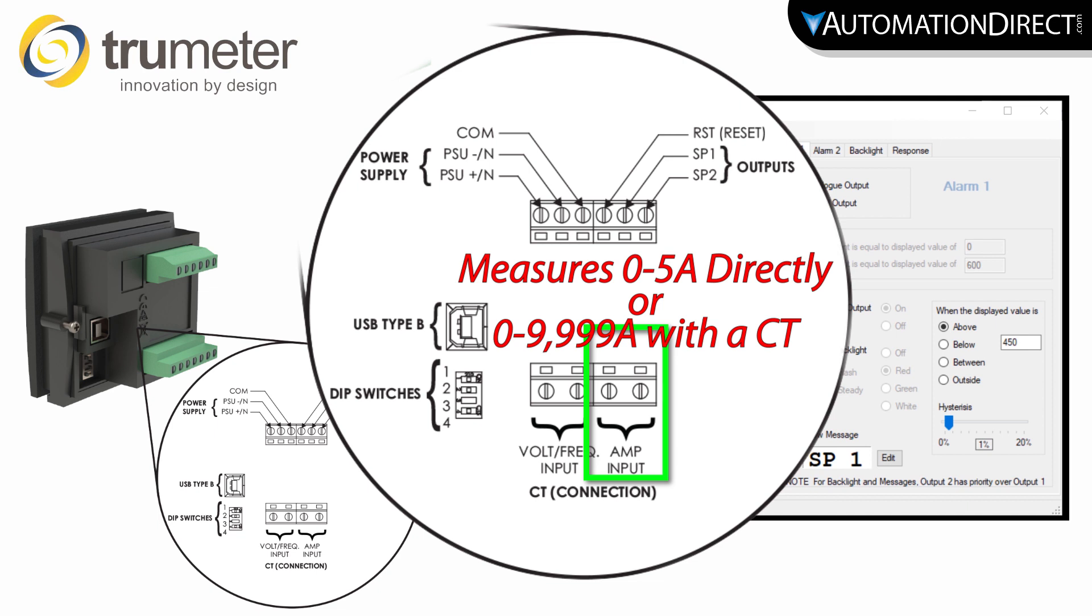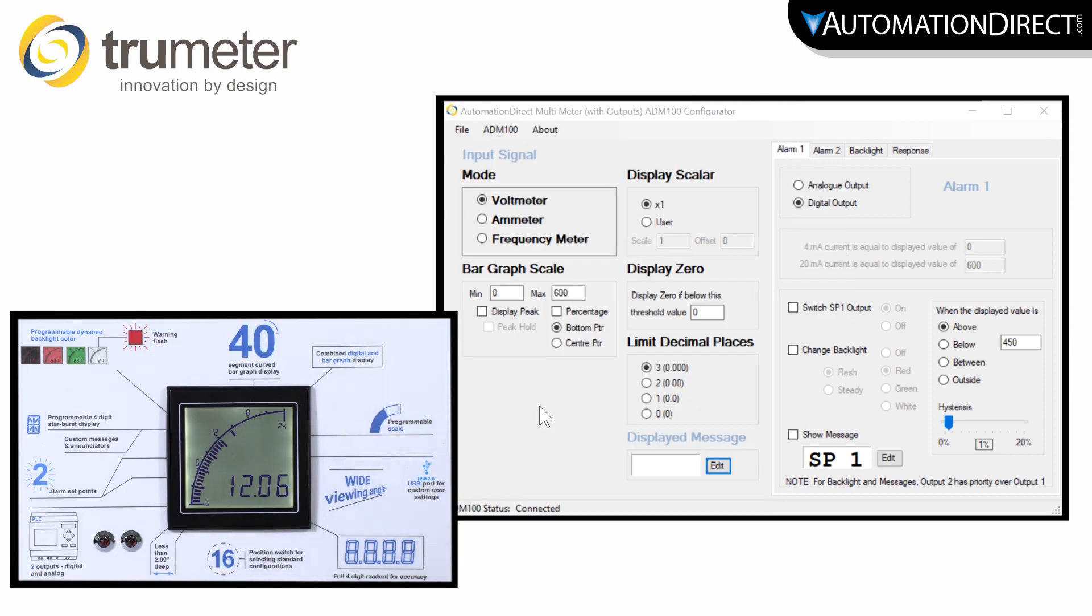This meter will measure up to 5 Amps directly, but if your process is more than 5 Amps, you will need to use a current transformer. Once you have your panel powered and the input wired, open up the configuration software.